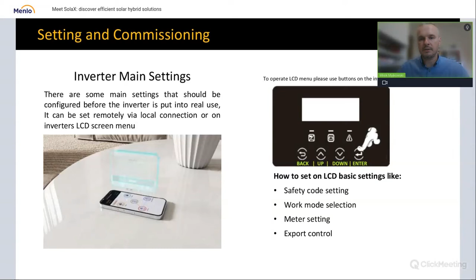Right, safety code. On the LCD screen you have 4 buttons: back, up, down, and enter. Press enter, go to menu, to the settings, enter the password that for installer by default is 2014-2014, and press enter. First on the advanced settings from the top is the safety code - enter into that safety code, and then you can see what it is now. If it's correct, then you do nothing.